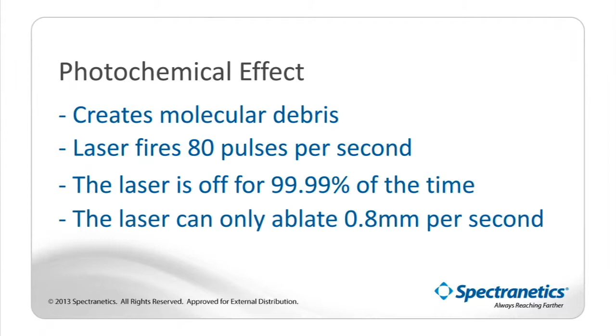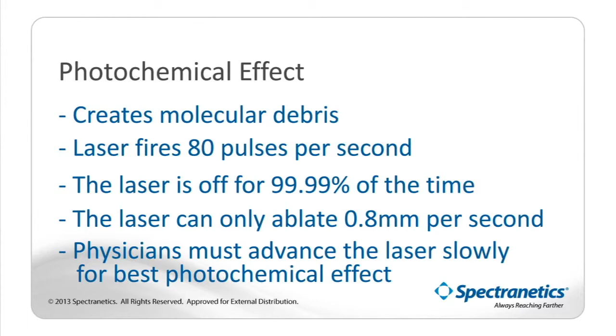Secondly, if we do the mathematics, each pulse can penetrate roughly 10 microns. We're giving 80 pulses per second. So if we convert this to millimeters, we can only photochemically ablate 0.8 millimeters a second. And herein lies the single biggest problem in terms of training physicians to use the laser. You must advance it very, very slowly. If it is advanced quickly, it does not have the best effect, which is this photochemical effect.